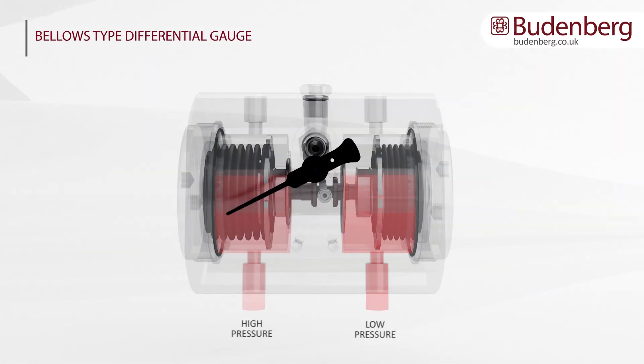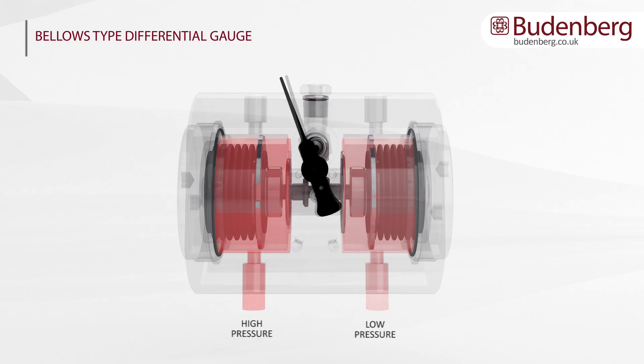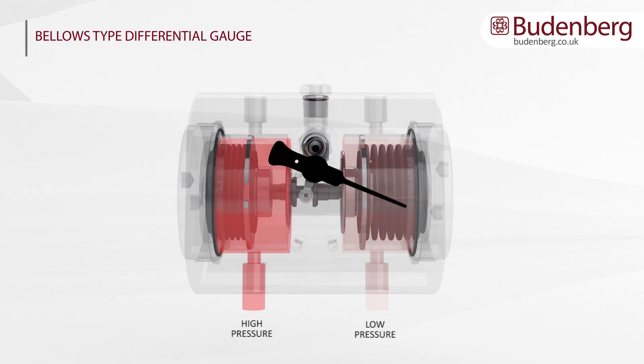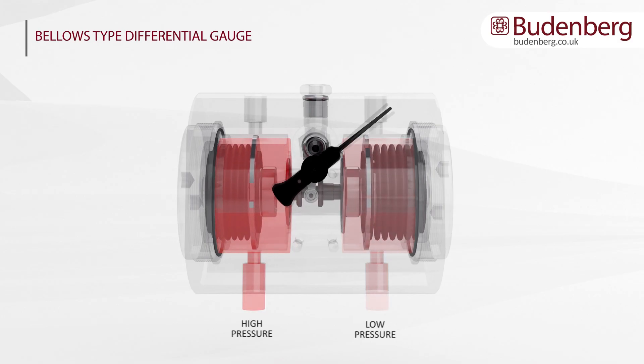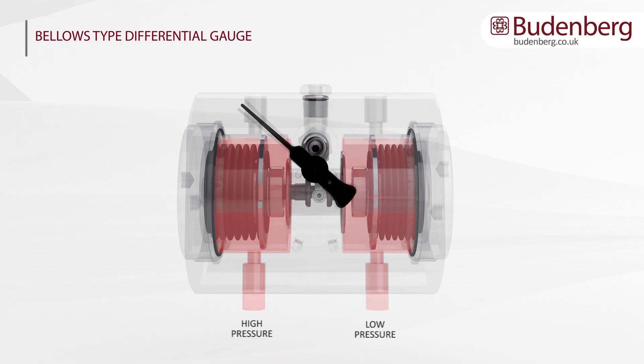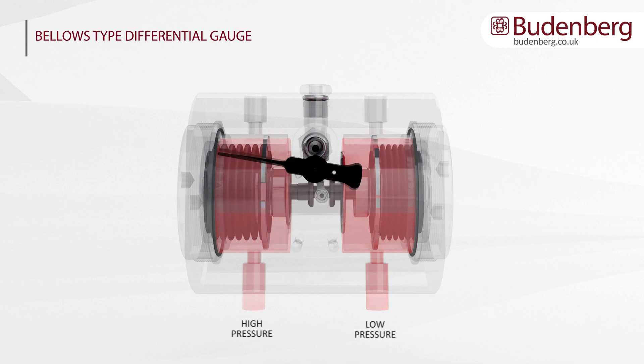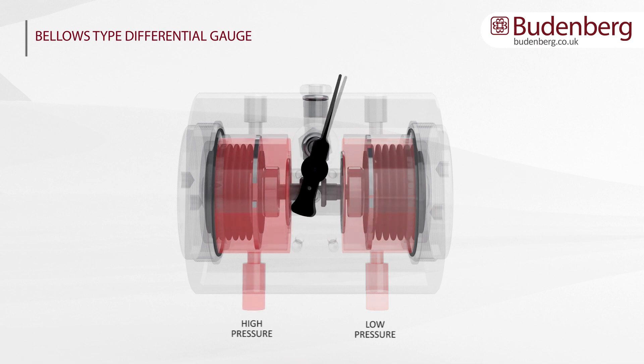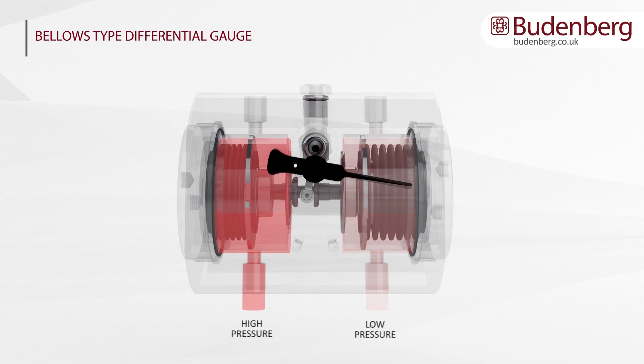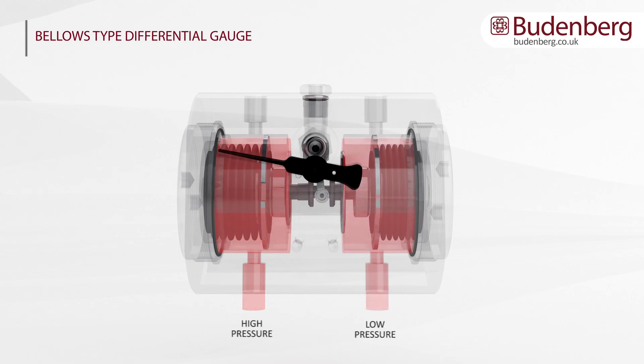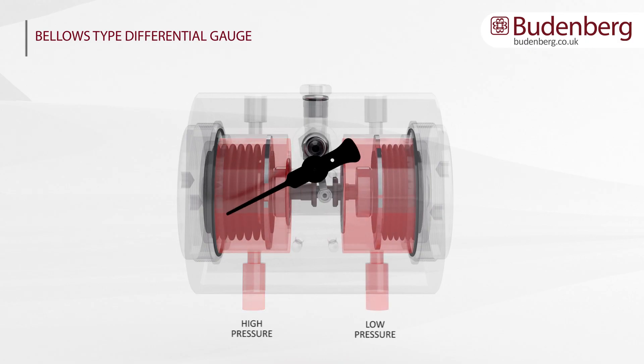Designed around a balanced bellows system which converts the differential pressure into a rotary movement by way of a torsion tube assembly and mechanical linkages. As the pressure increases, the bellows are compressed, forcing the pointer and mechanism to move.